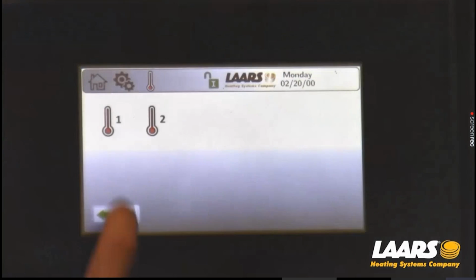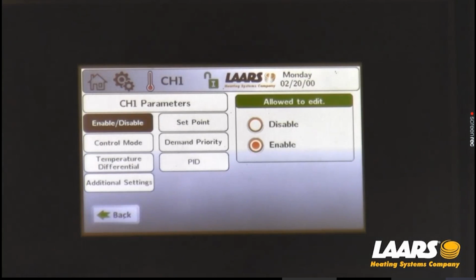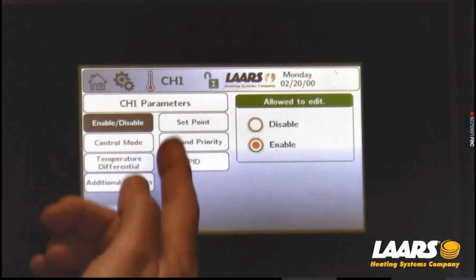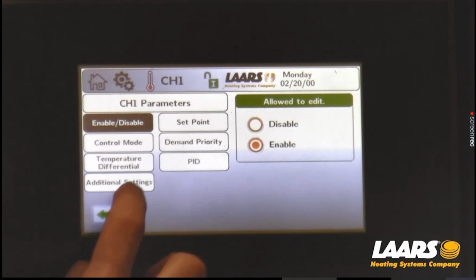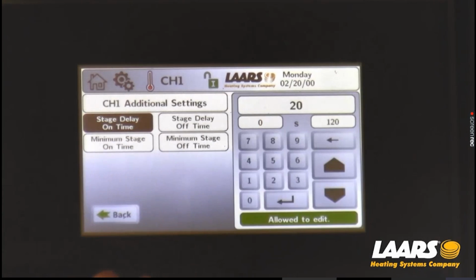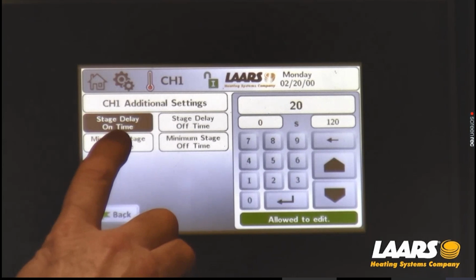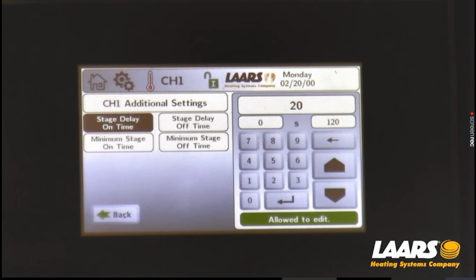Central heat set point, I'm going to choose first stage, first one. And as you can see, we've got some of the set points here. Under additional settings, I can get in and set my stage delay on time. Again, I want each gas valve to come on quickly, or fairly quickly. This should be defaulted around 60 seconds.